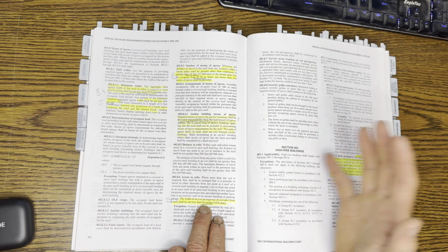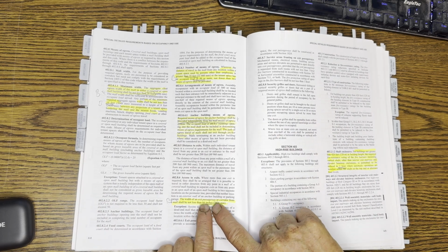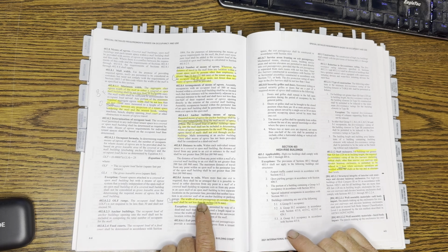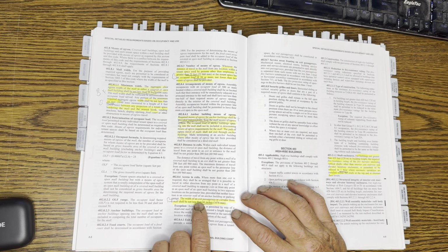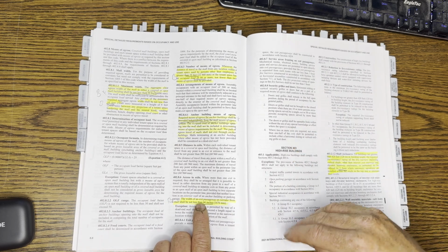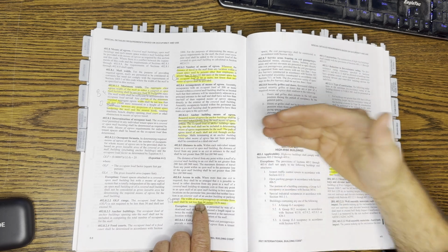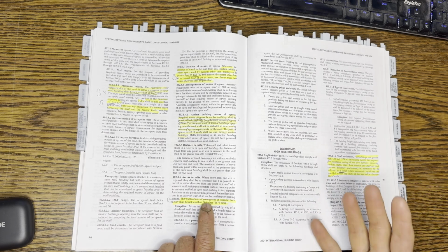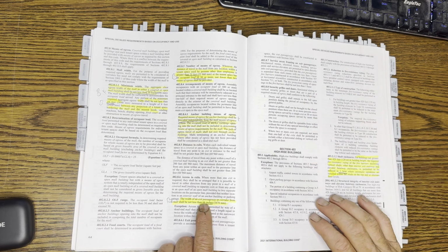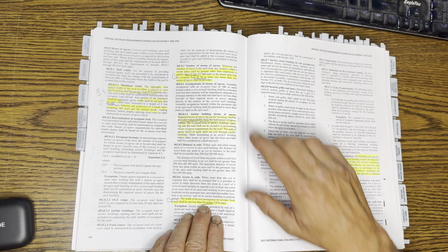You can't have any penetrations into an exit passageway. It has a very specific definition. See how that's italicized? That means it's defined in Chapter 2. But they don't do a very good job defining these things, so I want to explain this. Exit passageways have fire-rated construction, and once you're in the exit passageway, you're effectively in an exit. So you've crossed a fire-rated door into an exit passageway. That's how they achieve the 250 feet exit access travel distance requirements. I think it's 250 or 300. I'll look in Chapter 3.